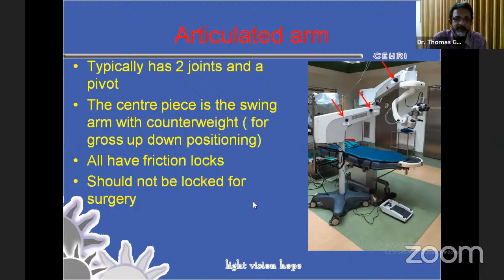One thing that most of us are unaware of is how to balance the microscope. You have a knob at the back end of the swing arm with a plus and minus on it, and this is turned to increase the leverage of the counterweight. There's a huge counterweight in here which is balancing the microscope's up and down movement like a seesaw. You do not want to drop the microscope onto the patient, so this has to be adjusted perfectly.